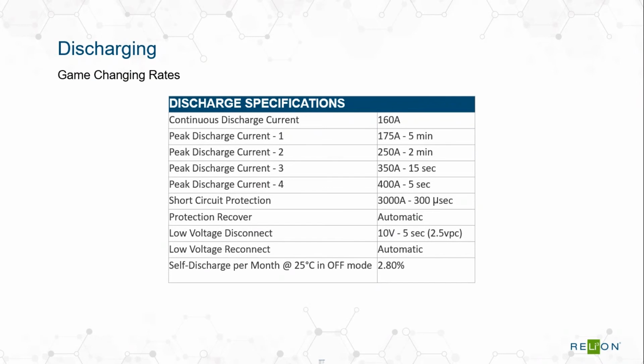Otherwise they're not in the nice small form factor of the Insight battery. We also list multiple peak discharge currents, and I think this is important, because with some appliances you might run, it's not just 160 amps continuous or 400 amps for 5 seconds. We like to give everyone an idea of the ranges here and where our software is programmed to turn the battery off if they exceed those rates.